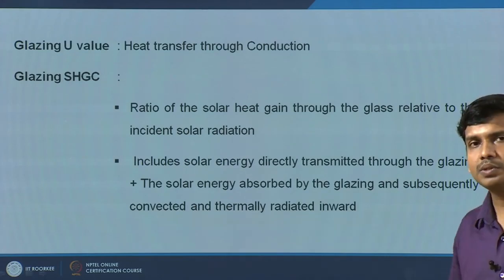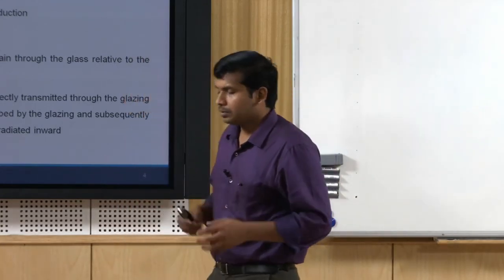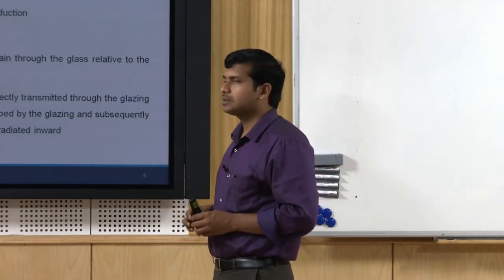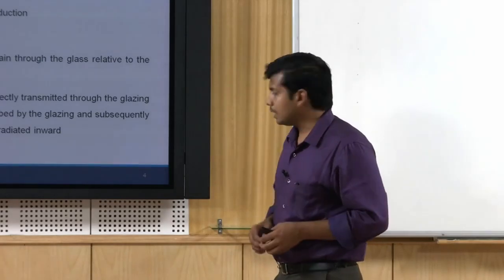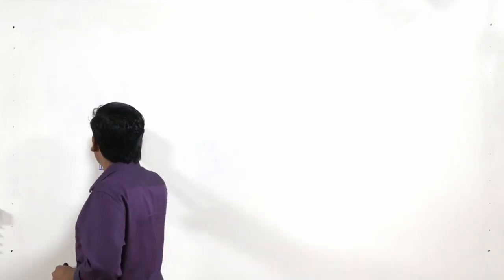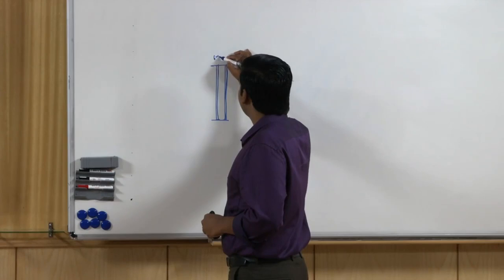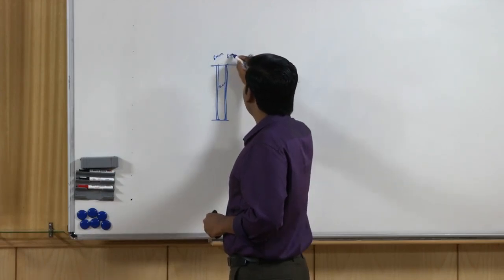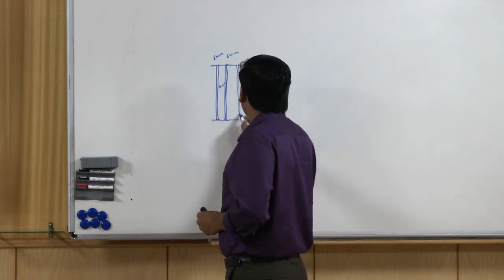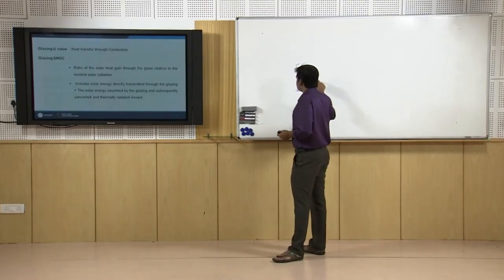The glazing U value is the first property we usually refer to — it is heat transfer through conduction, same as for the opaque wall system. It tells you how much conductive heat flow happens through the glazing system. Imagine a 6 mm single glass system versus a double glass unit with a 6 mm, 12 mm air gap, and another 6 mm layer. As you increase the number of layers to a triple glass system, the U value starts coming down.